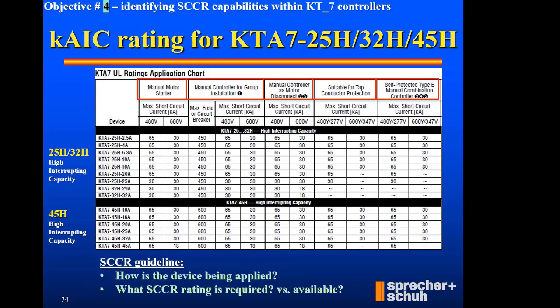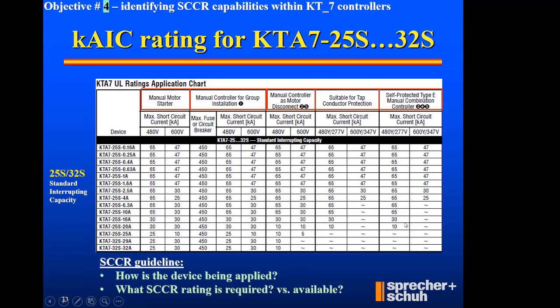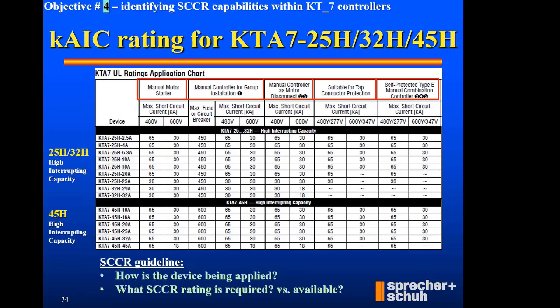Let's just jump all the way over to the right because we were talking about self-protected type E. This table's set up on the same page, so you have those five applications across the top. But going over to self-protected type E, previously I was only getting 10 KAIC with a 20 amp model. I'm looking at a 25H 20 amp model. Instead of 10, I've got the potential for 65 KAIC. That's what high interrupting capacity did for me on that option selection.